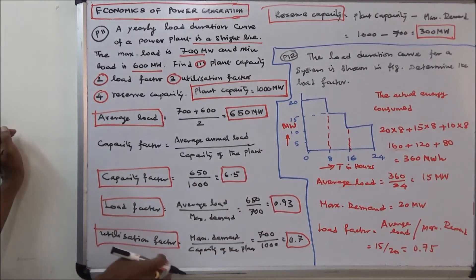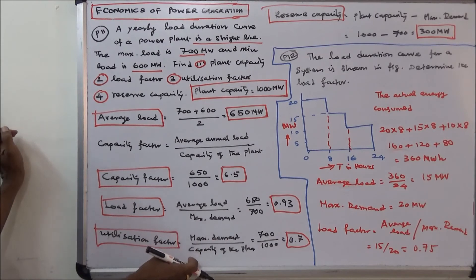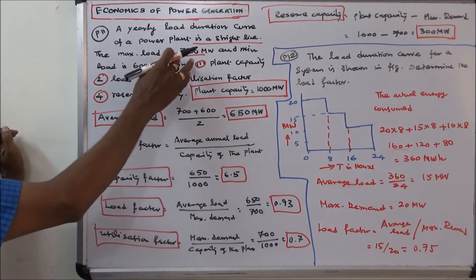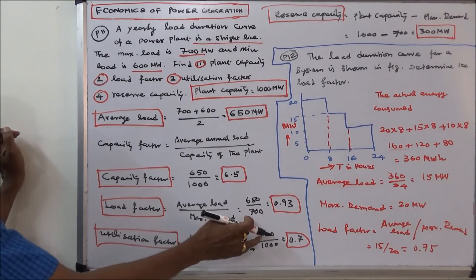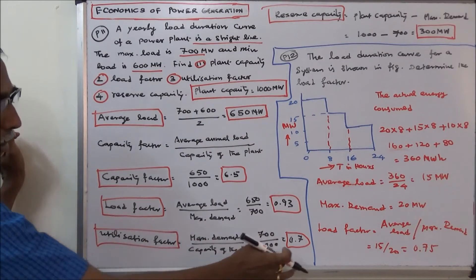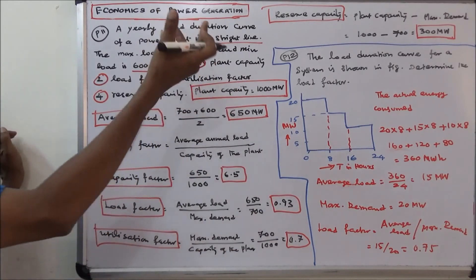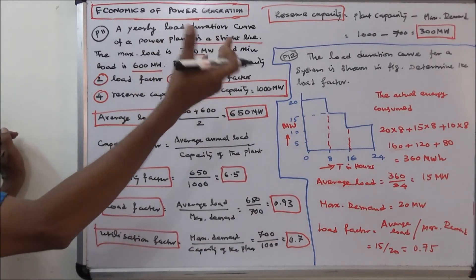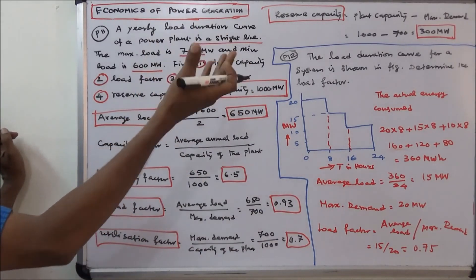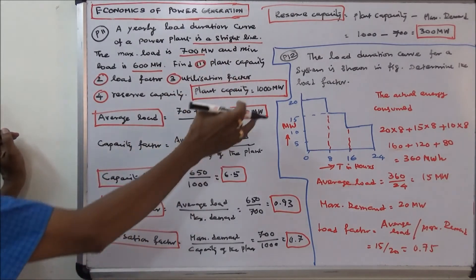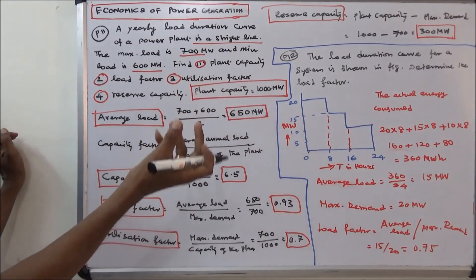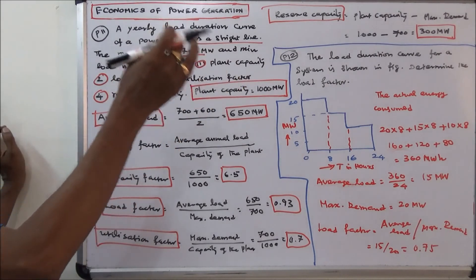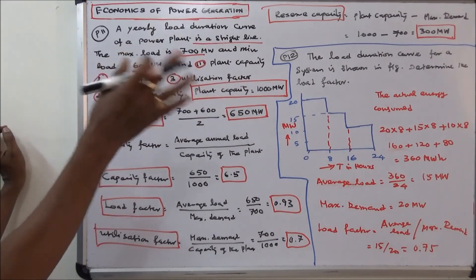Utilization factor equals maximum demand divided by plant capacity: 700 divided by 1000 equals 0.7. Reserve capacity equals plant capacity minus maximum demand: 1000 minus 700 equals 300 megawatts.